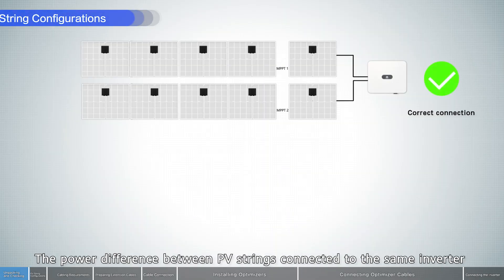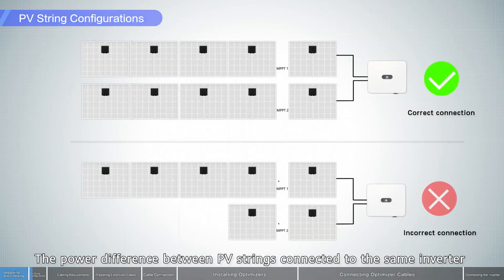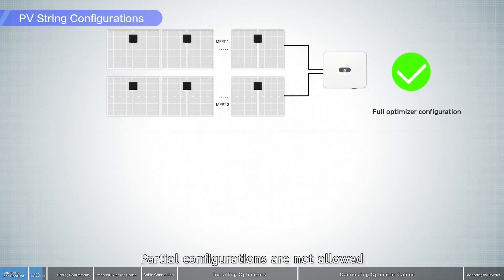Check that the cables of optimizers correctly match those of PV modules. The power difference between PV strings connected to the same inverter must be less than or equal to 2 kilowatts. Otherwise, the inverter may be derated. Partial configurations are not allowed.